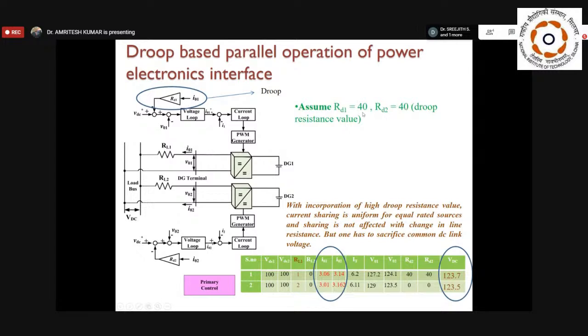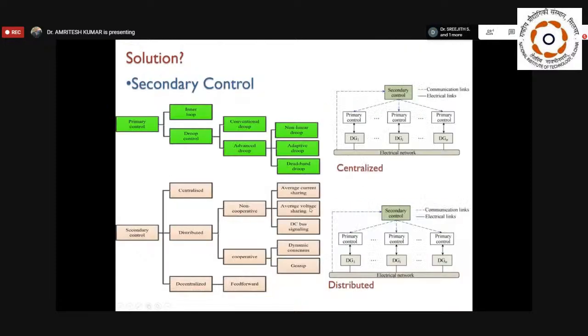So we have to fix an optimum value of the droop resistance. There are adaptive droop controllers also. You will find a lot of research papers on adaptive droop, deadband droop, nonlinear droop, where the droop value keeps changing based on the condition. Suppose the line resistance changes with temperature; accordingly the droop has to be adaptive so that the sharing stays uniform. These are advanced controls devised within the primary control to get the optimum result. You'll find a lot of research there.